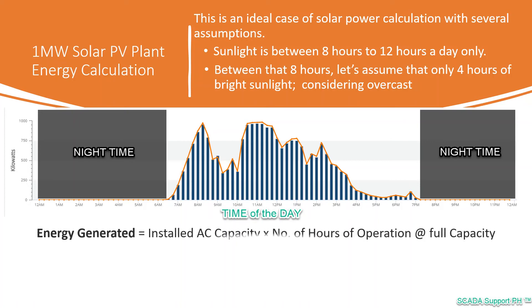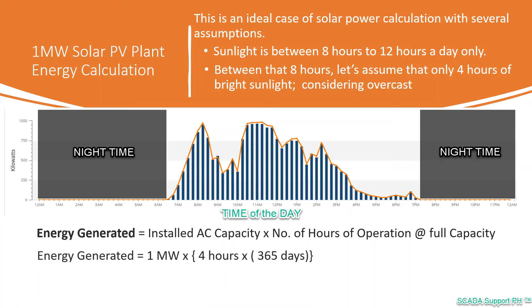We use the system to calculate the energy generated as a product of the installed AC capacity, or system size, multiplied by the number of hours of operation at full capacity. That is 1 megawatt times 4 hours multiplied by 365 days, giving us 1,460 megawatt hours or simply 1.46 gigawatt hours of energy generation.